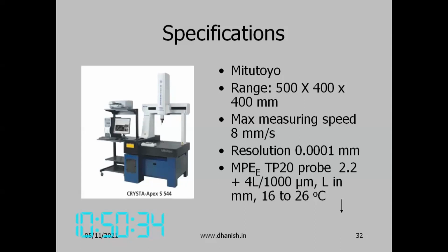And then the distance moved is proportional to L. So L is the length moved. So that is 4L by 1000 micron. So this is the accuracy achieved if the temperature is maintained between 16 to 26 degrees Celsius. So you can see that the accuracy is minimum 2.2 micron. So even if L is 0, it is not uncertainty, it is the maximum permissible error of plus or minus 2.2, and again, I think this is 95% accuracy. So 2.2 micron is only the accuracy of the CMM.